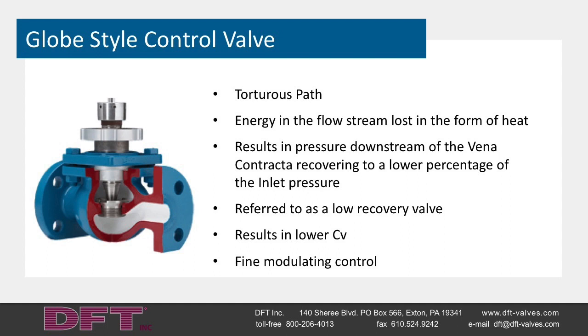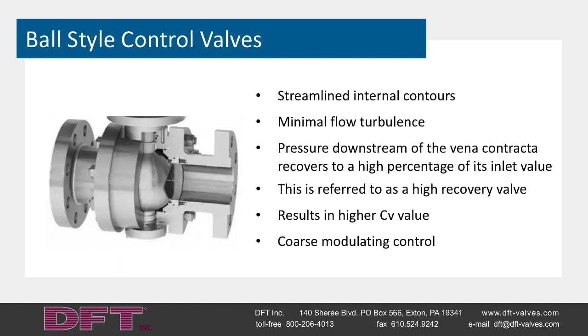Globe-style control valves — the most common type of control valves — require the flow to follow a tortuous path as it proceeds through the valve body. The tortuous path creates turbulence that extracts energy from the fluid and results in an increased pressure drop. These phenomena impact the CV, resulting in lower flow than other styles of control valves. This is referred to as a low recovery valve design. Although the globe-style control valve provides lower CV, it does provide fine modulating control.